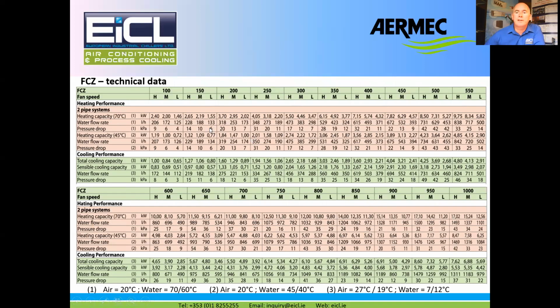The range of fan coil units is typically about 2 kilowatts up to about 15 odd kilowatts at nominal conditions. Please be careful. People are often claiming to have certain capacities, but if you play with the data, you can claim all sorts of stuff. By the way, Aermec are Eurovent certified. So their fan coil units are independently tested, independently verified. So basically it does what it says on the tin. Some manufacturers are not Eurovent certified. They can say whatever they want. It's not independently verified, so do watch out for that.